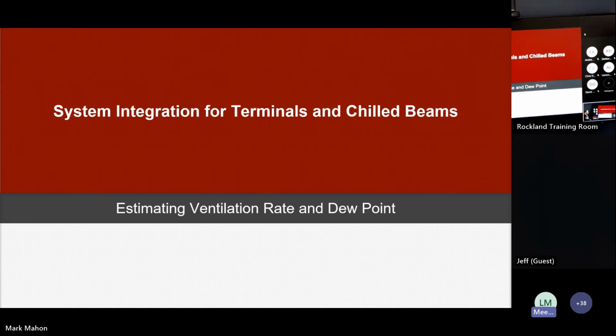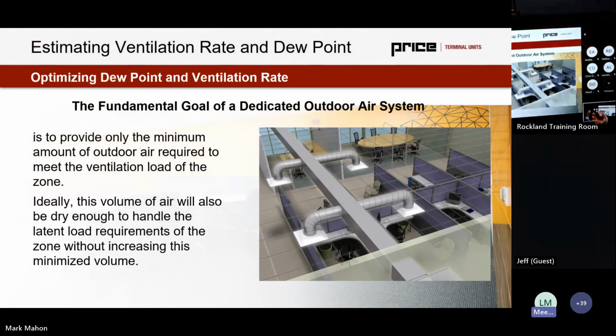So my next section, I want to talk a little bit about estimating ventilation rate and dew point. When we look at a DOAS system, the fundamental goal from a zone consideration perspective is that we would like to provide only the minimum amount of outdoor air required to meet the ventilation rate of the room. Now, we still have to worry about latent loads. We still have to maintain a comfortable humidity within the space. So the gold plating of this type of design from a zone perspective is, let's try to handle the latent load requirements of the zone without increasing that volume further.